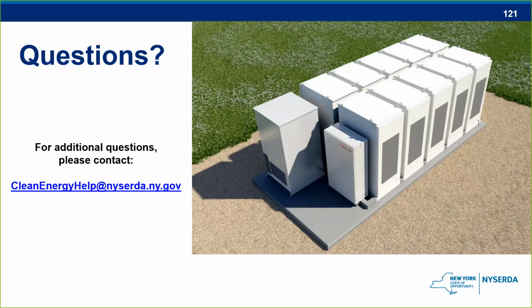All right, thanks, guys. We've got two more questions. If you don't mind, we'll just run through those quickly. Thoughts on using gas detection for lithium-ion energy storage systems? This is going back to that 20 megawatt-hour example. That's an installation that's remote. It seems like it's five 4 megawatt-hour containers. So thoughts on using gas detection for lithium-ion as an effective early detection means to catch thermal runaway early in its tracks? Do you recommend?